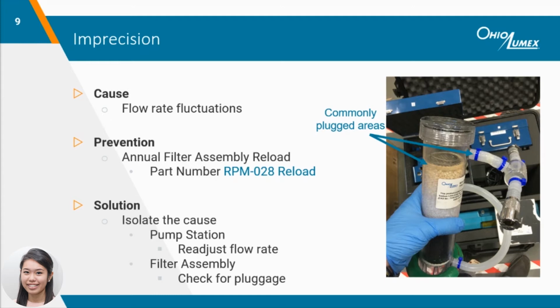If fluctuations only occur when the filter assembly is connected, the most common location for pluggage is at the intake or the filter pad shown on the photo. You can check for a clog by carefully removing the silicone tubing and the glass tee from the intake. If the intake is clogged, work in a fume hood and use a thin and rigid object to carefully unclog the filter. If the intake is not clogged, the filter assembly may need to be refurbished or replaced.